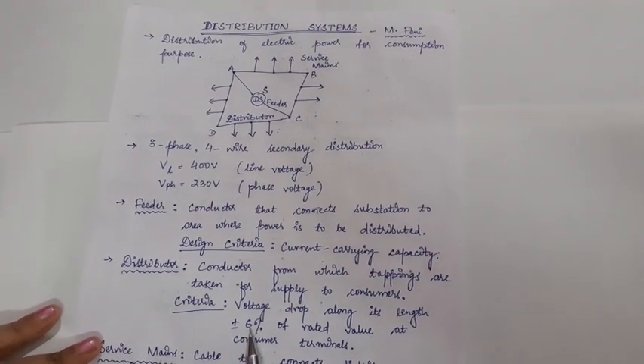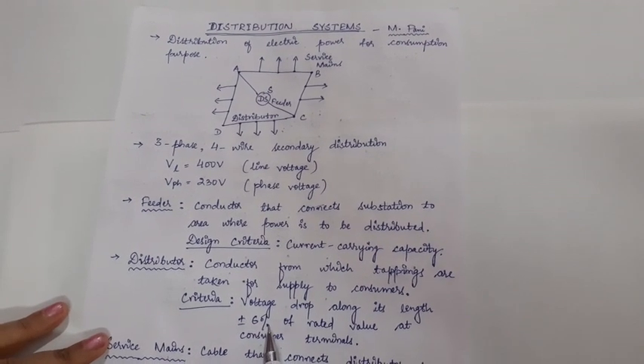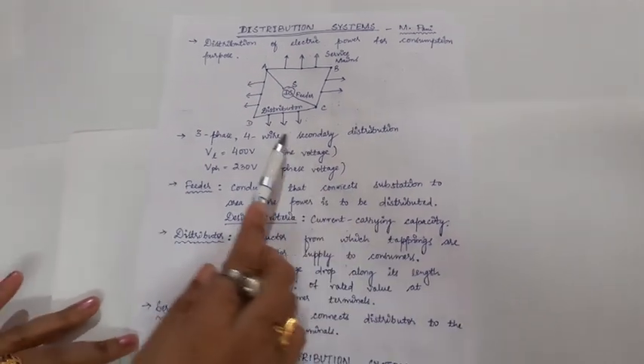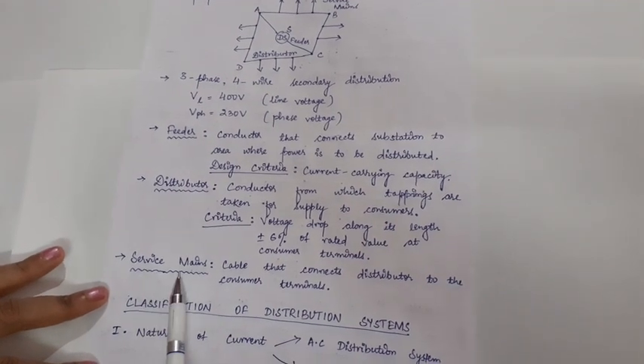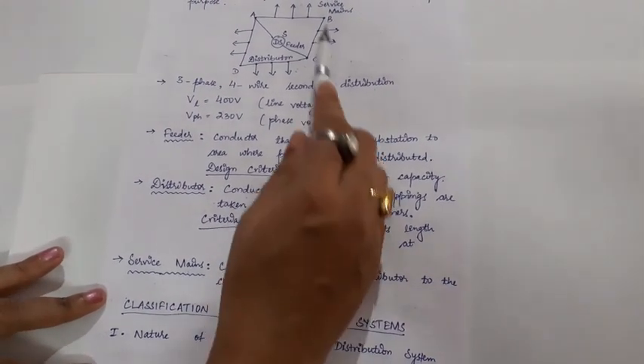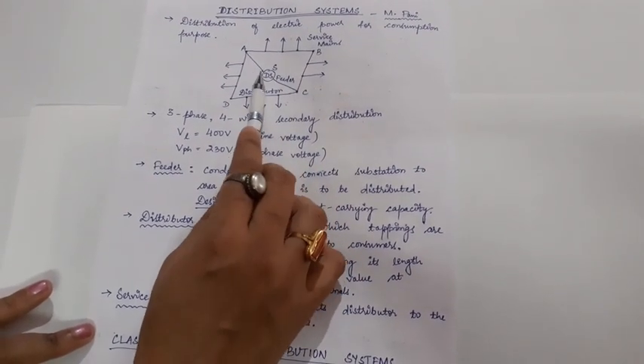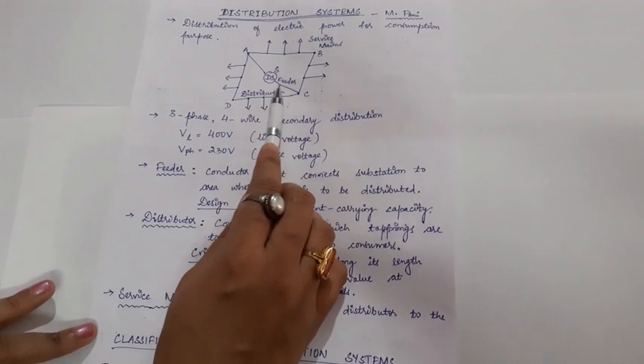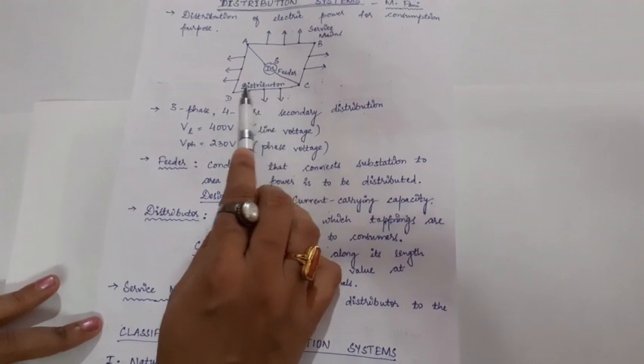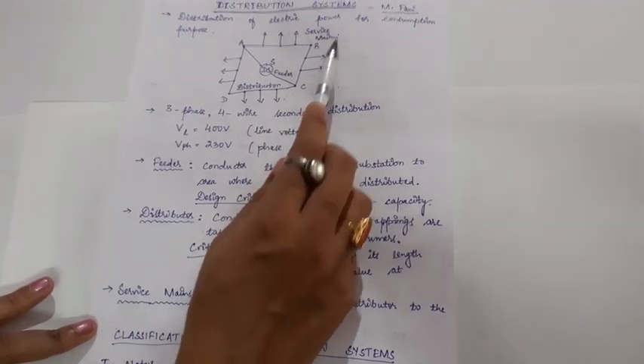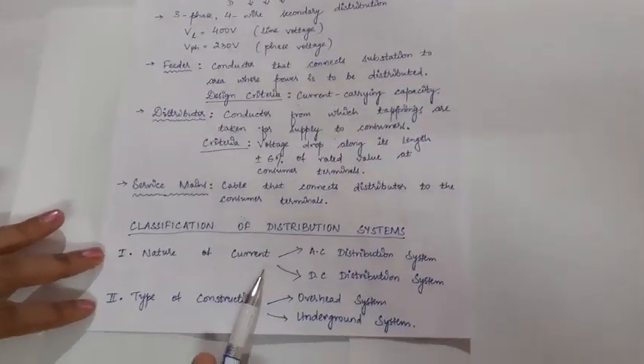The voltage drop should be plus or minus 6% of the rated value at the consumer terminals. From the distributor, the cable that connects the distributor to the consumer terminals is called the service mains. So from the distribution substation, the conductors arising are the feeders, then the conductors connecting to feeders are the distributors, and from the distributors, the tappings taken are called the service mains.